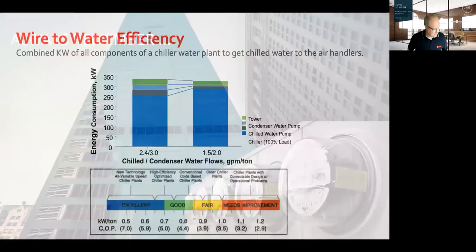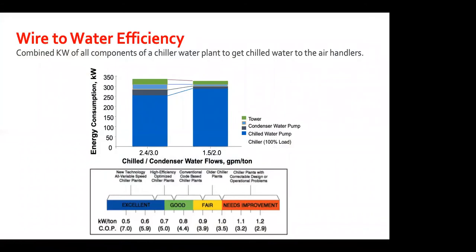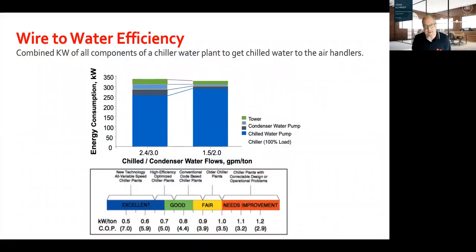Thanks, Craig. That was a good overview of the chiller plant and primarily the chillers. This slide kind of depicts how much energy each component of the chilled water system, at least in or around the chiller plant, takes up. We have to look at all of them, as Craig mentioned. We have the chiller itself, which is the bulk of it. Although chillers with VFDs and the inlet vanes that we've had for years are getting about as efficient as we can.